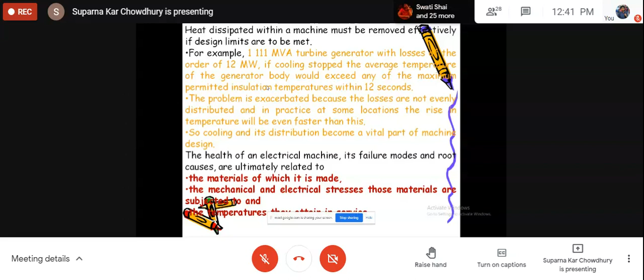Now, when we are monitoring the health of an electrical machine, its failure mode and root cause are very important, which will depend on the material of which it is made, the mechanical and electrical stresses those materials are subjected to, and the temperature attained during operation. For electrical machines, these are the different parts. There is the enclosure, which is the frame, then the heat exchanger, the electrical connections through which it is connected to the external circuit, that is the bushings or the terminal box, and there are the bearings also, which are part of the frame, the bearing enclosure.